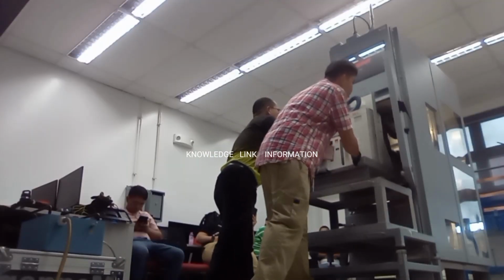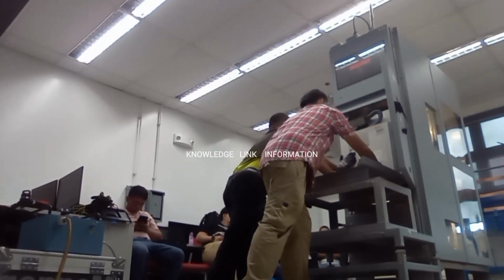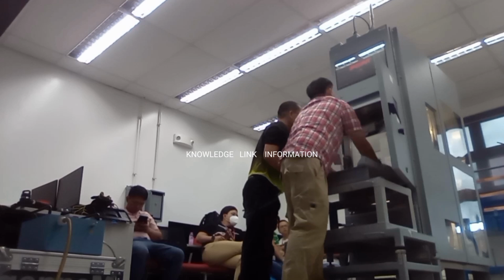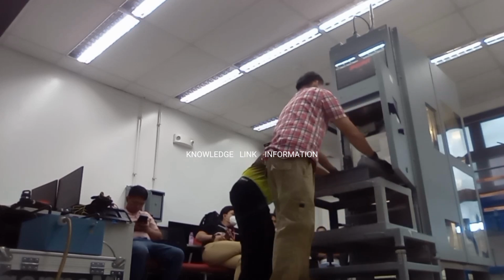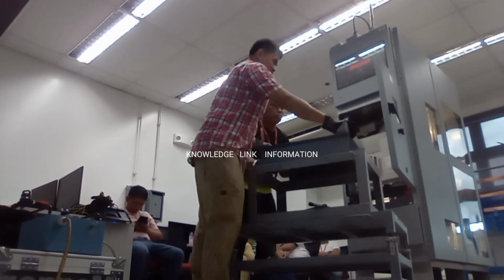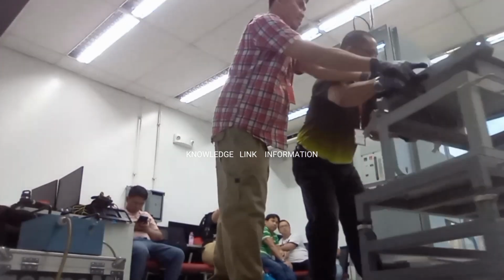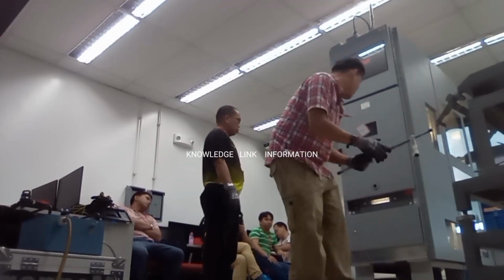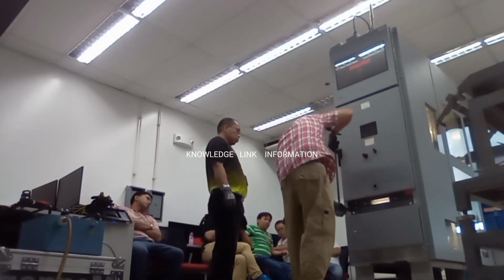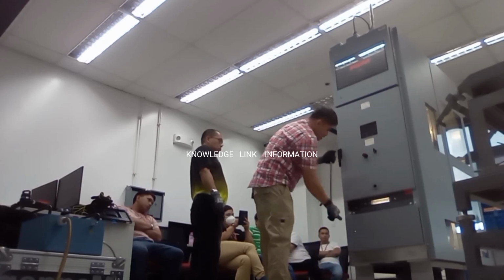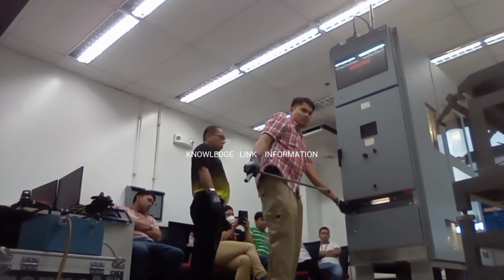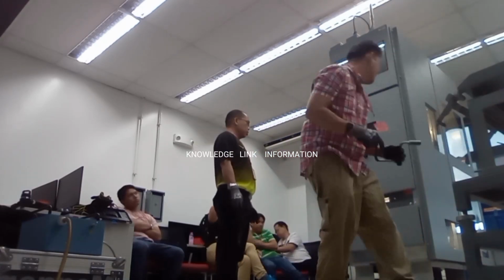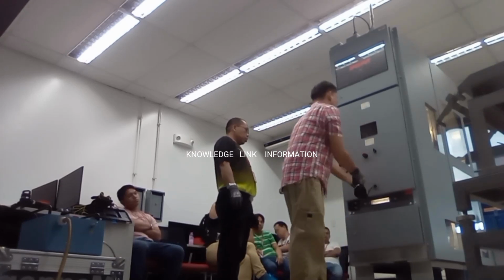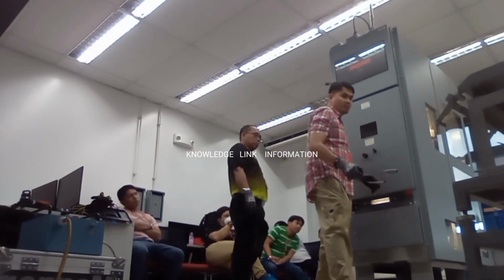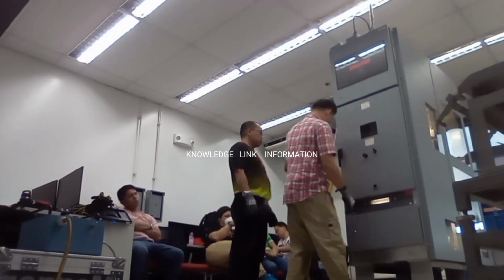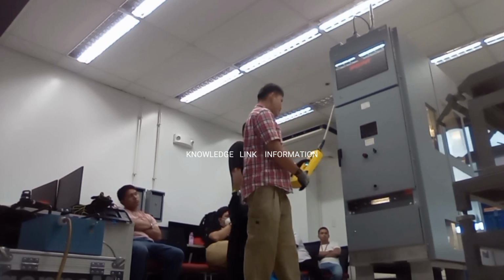Number 23. Go back again to the switchboard and install the high-voltage breaker with the control line plug in the switchboard socket, once all bus bar earthing connections have been removed. Number 24. Pick up the special tools and disconnect the circuit earthing switch from the bus bar phases. Number 25. Rack in the high-voltage circuit breaker, and switch on the breaker using the push button to energize the bus bar.